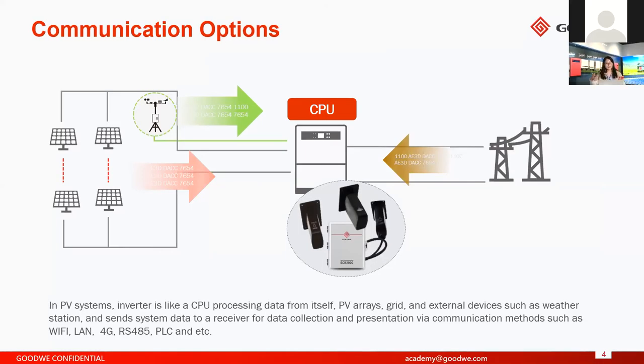As you know, in the PV system, the inverter is like a CPU. It is processing all data from itself inside, from PV arrays, from the grid, and from external devices, such as weather station sensors. And it sends the data to a receiver called a data logger for data collection, and then it will transfer to a server which contains mass data, and then the mass data will be presented on a platform called a PV plant monitoring platform.